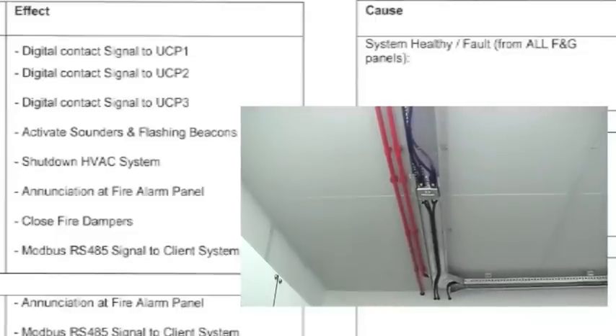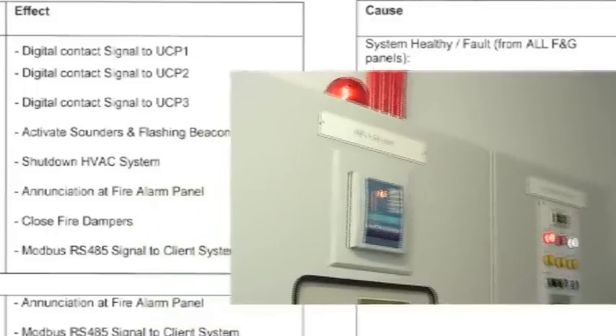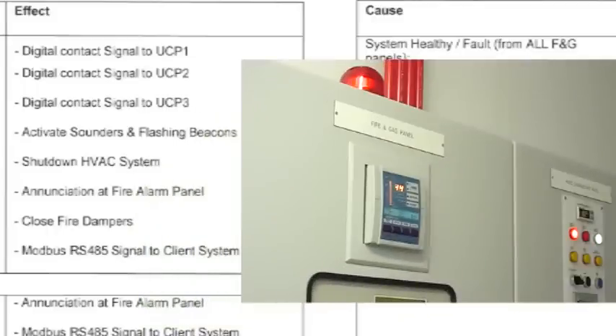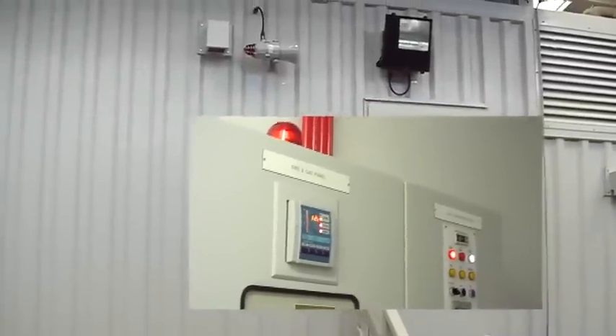For example, in the event that a confirmed fire is detected in the LER by VESDA, the system will operate as follows. Digital contact signal to UCP 1, 2 and 3. Activate sounders and flashing beacons. Shut down the HVAC system. Annunciation at the fire alarm panel. Close the fire dampers. And also send a Modbus signal to the customer's system via serial link.